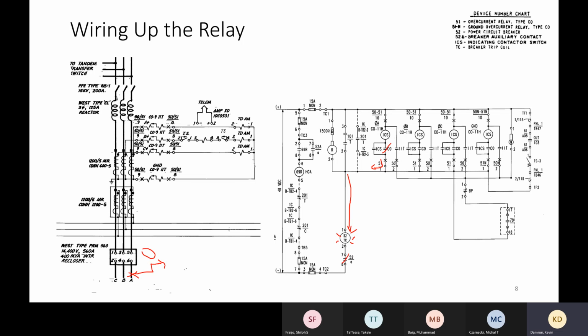Because normally when the breaker is closed, that 52A is closed. So that contact is there so that when the breaker trips, I de-energize the trip coil so that I don't burn that trip coil up. Once the breaker's tripped, there's no reason for holding that circuit in, right? Does that make sense? Yes. Okay.